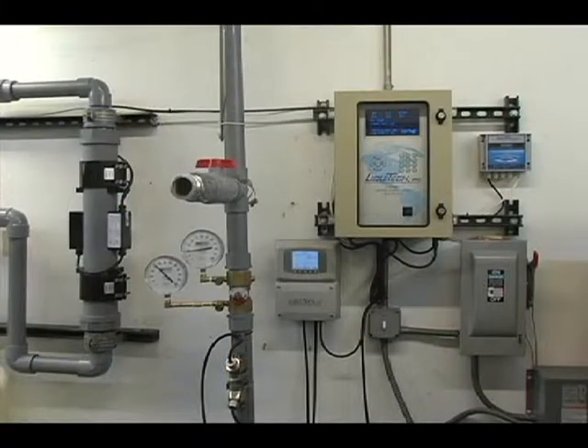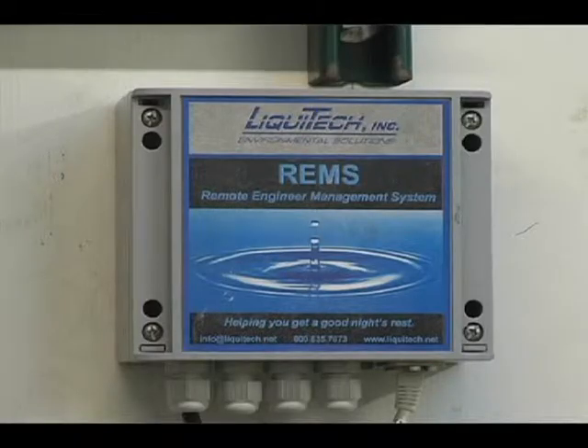The latest generation LiquiTech Ionization Systems are composed of four main components: the controller, integrated ultrasonic flow meter, the REMS supervisory control module, and an ionization chamber. The flow meter, using ultrasonic technology, measures the amount of water to be treated and continuously sends a flow signal to the controller.